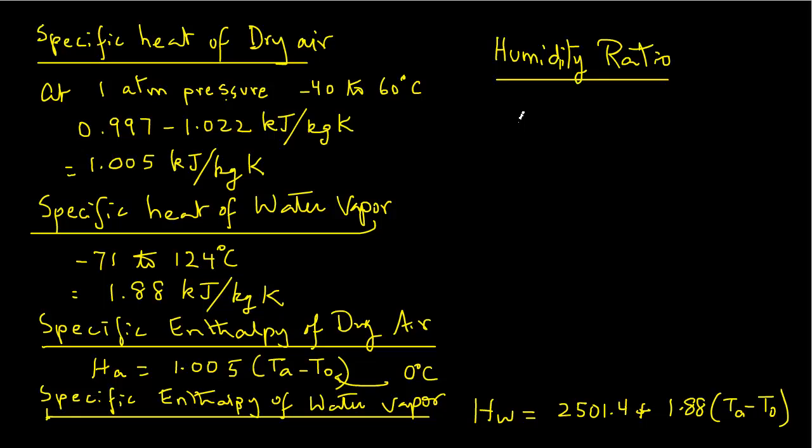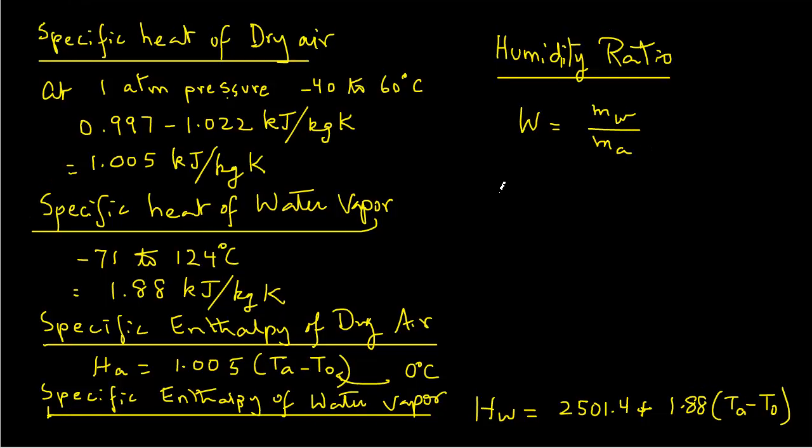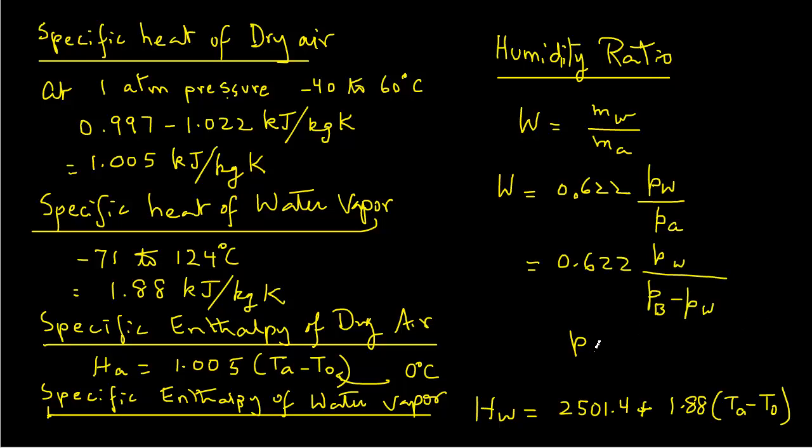Humidity ratio is defined as the mass of water vapor per unit mass of dry air, where W, the symbol for humidity ratio, equals MW over MA. M is the mass, and this can also be written as W equals 0.622 partial pressure of water divided by partial pressure of dry air, and that can also be written as 0.622 PW over PB minus PW. Note that from Dalton's law, we know that PB equals PW plus PA, so we can write for PA, PB minus PW.